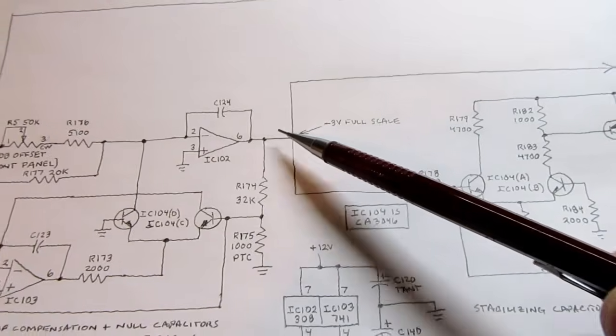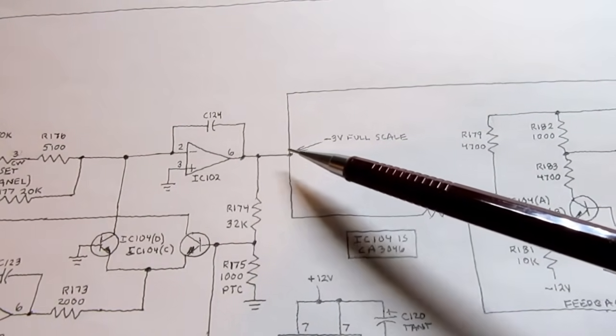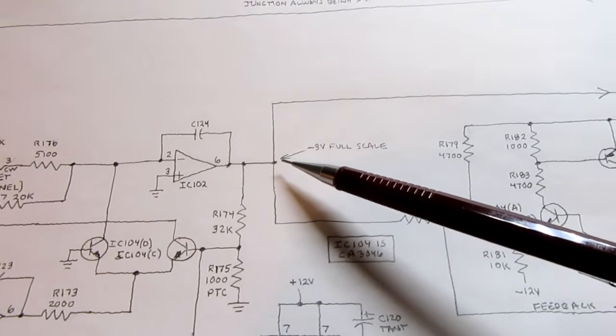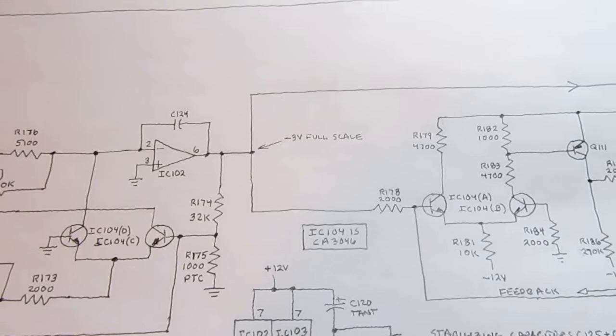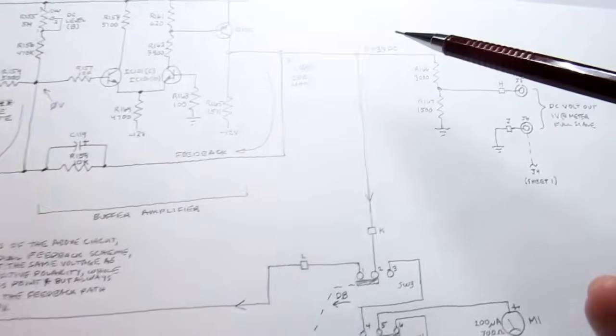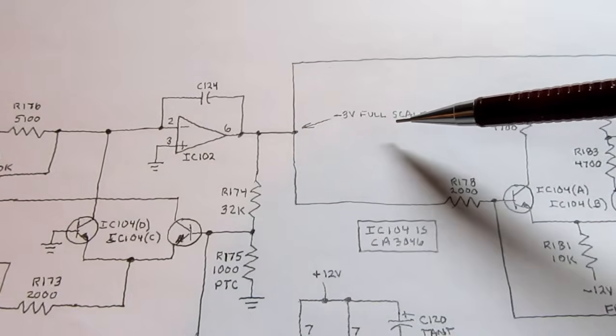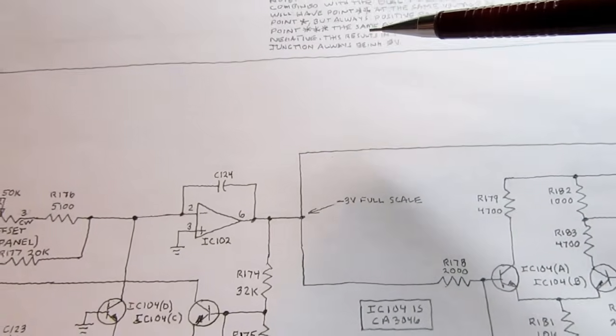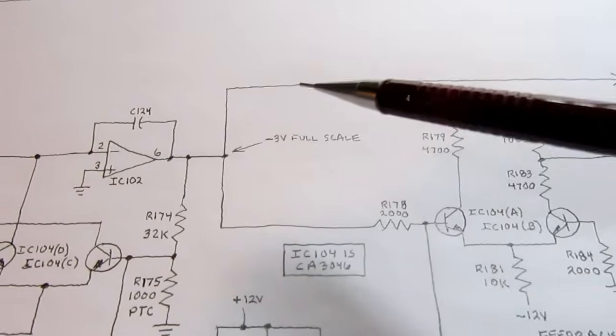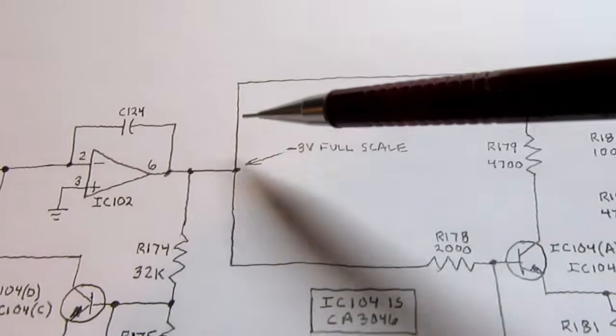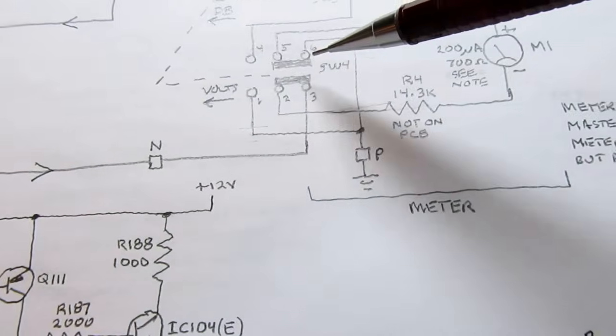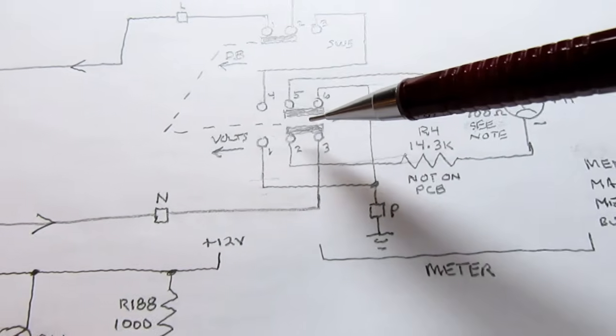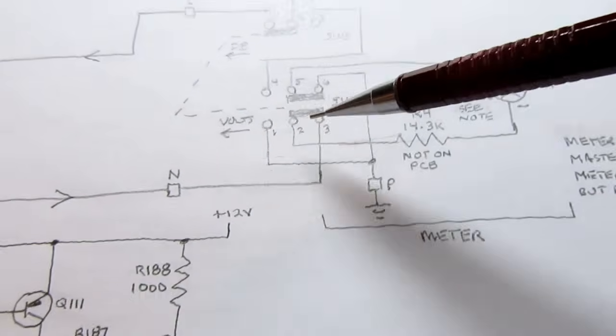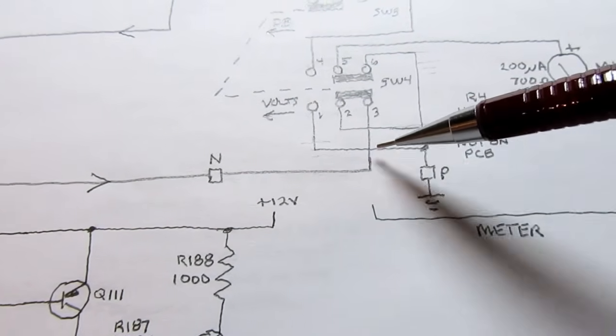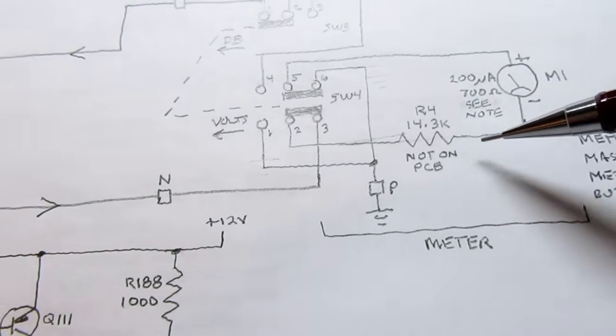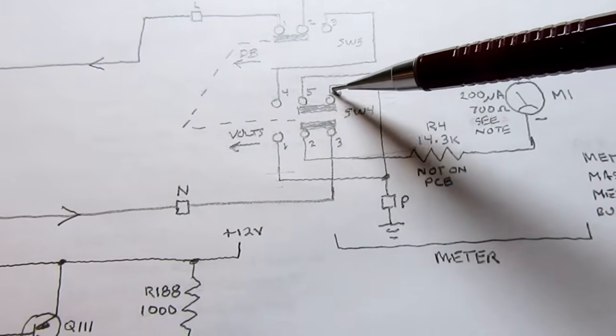So what we have over here, and this is the output of this overall circuit, this is a DC voltage, just like the signal coming into it was, and it's 3 volts at full scale, but it's negative 3 volts. It's been inverted from a positive 3 volt full scale to a negative 3 volt full scale, and it's also no longer the linear input, it's a logarithmic value. But 3 volts still means full scale on the meter. So we come out of there, and we go through here, and we go into this switch. Again, assuming we're in the dB mode, this switch is already shown in the dB mode. So that 0 to 3 volt signal comes in here, goes around, goes through the resistor, goes through the meter movement, comes back here, loops around, and goes to ground.